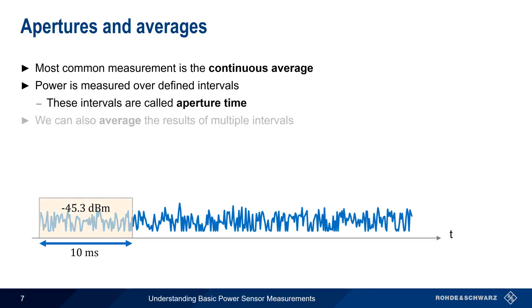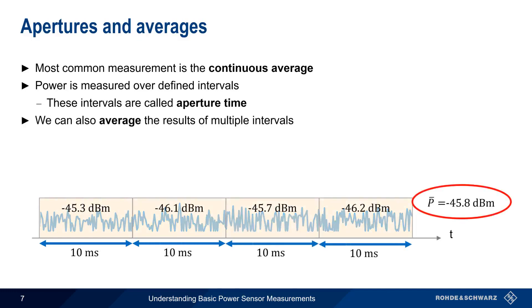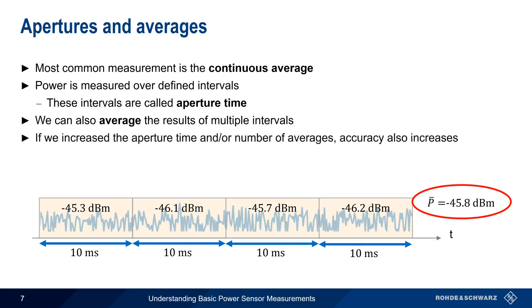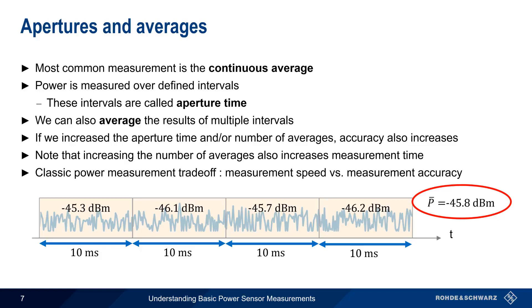After zeroing the sensor, we reconnect to the source and execute the measurement. Most of the time, power sensor results will be displayed continuously, or what's called a continuous average. Essentially, this means that power is measured over defined intervals called aperture time. We can also average the results from multiple intervals. Aperture time and average count are important parameters because increasing aperture time and/or the number of averages also increases the accuracy of our measurement. However, increasing the number of averages also increases the time it takes to get a measurement — this is the classic tradeoff in power measurement: measurement speed versus measurement accuracy. In other words, the longer we measure, the more accurate our measurement result.